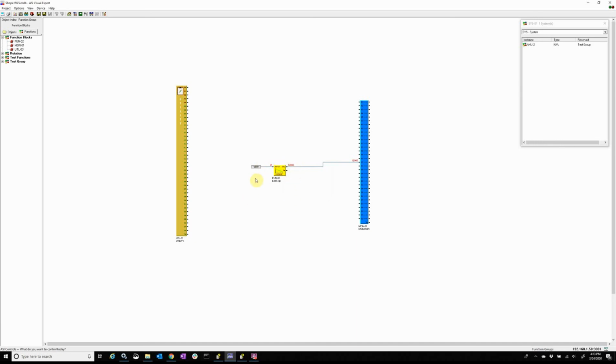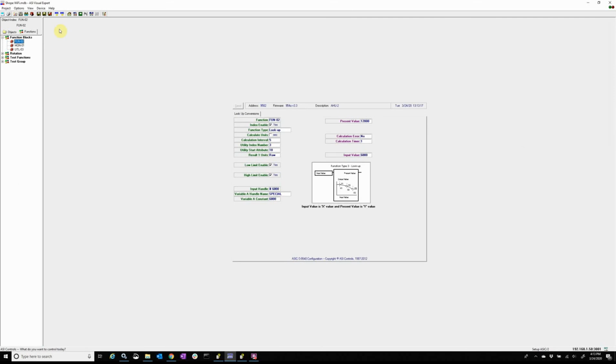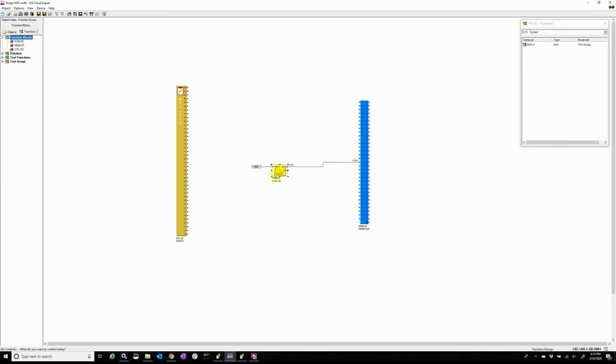And so any temperature above 60, it'll stay at 120 because we have our low limit and high limit blocks checked. And anything below 30, we will not go above 180. It is linear in between, so 45.23 degrees will give us somewhere in the middle, and it'll just go up or down from 120 to 180.